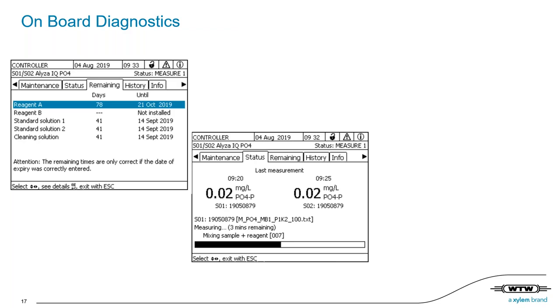Is the Alyza IQ suitable for saline sewage application and chloride content around 6,000 to 8,000 milligrams per liter? That's a good question, but this is really a limitation. So for saline water, as the material is for a certain specification also for the sample conditions. And if you have a high salinity, I would not recommend to use it.